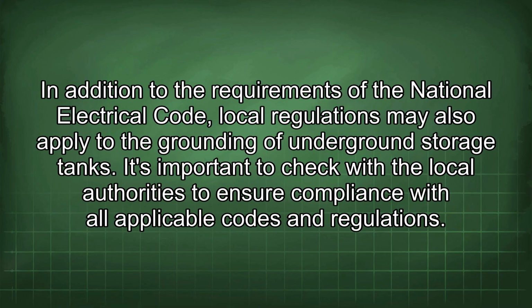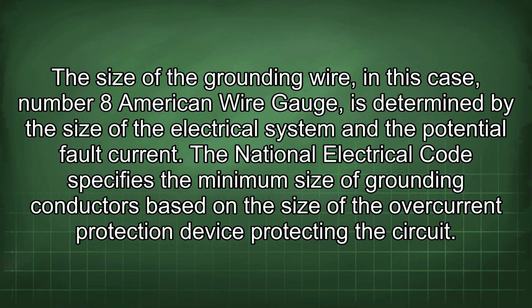In addition to the requirements of the National Electrical Code, local regulations may also apply to the grounding of underground storage tanks. It's important to check with the local authorities to ensure compliance with all applicable codes and regulations. The size of the grounding wire, in this case, number 8 American wire gauge, is determined by the size of the electrical system and the potential fault current.